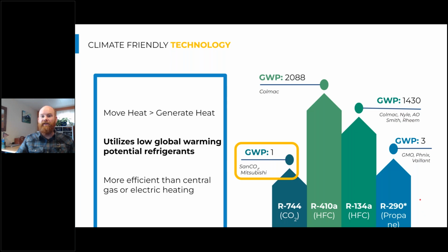Unfortunately, we're limited with the propane we can use in a heat pump, even though it's only a few pounds of propane in general compared to that 20-pound tank sitting out next to our barbecue. There's some danger and risk associated with that propane as it is flammable, and there's some red tape holding that up. But I see propane as a promising natural refrigerant that would be a great use for that fuel source. And we're not burning that propane in this case. We're just using it for the heat pump cycle. It would be the refrigerant. So a great opportunity there.